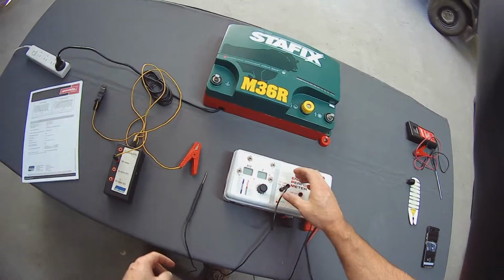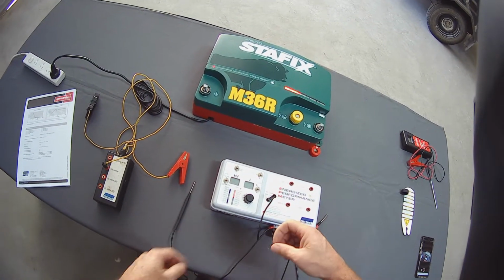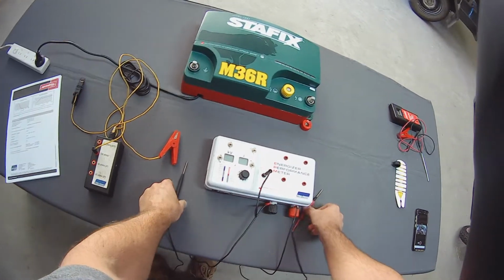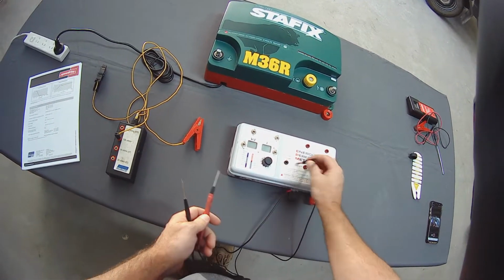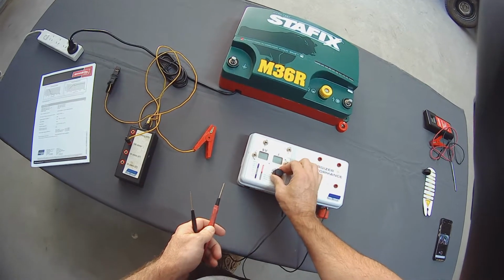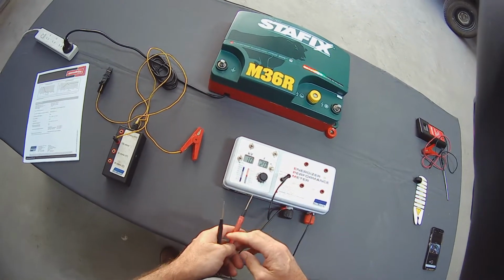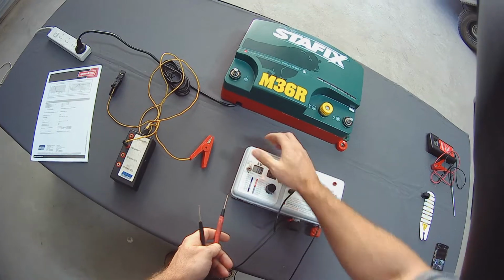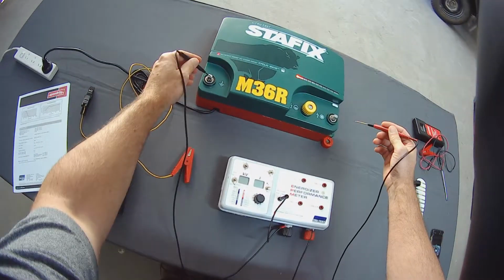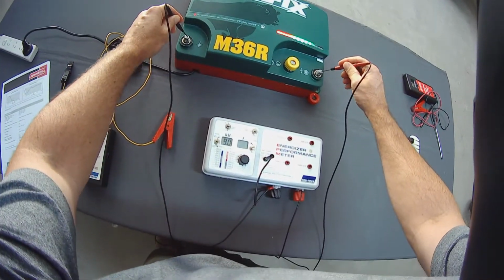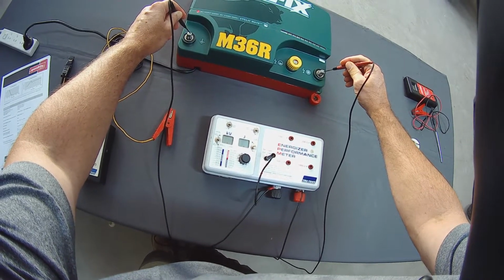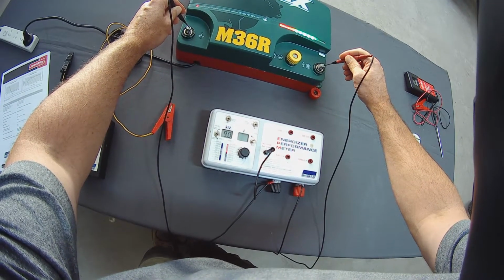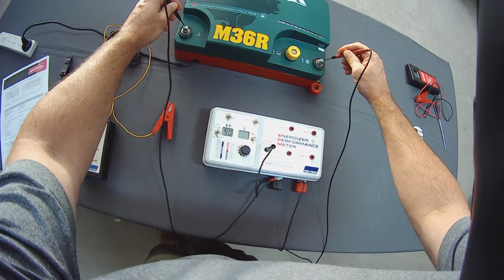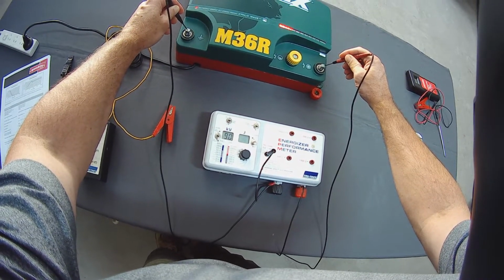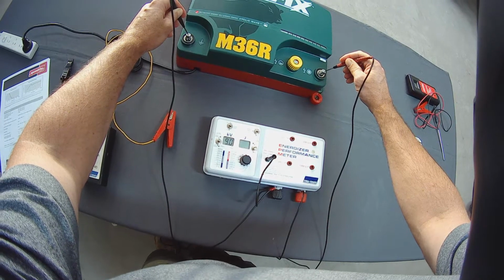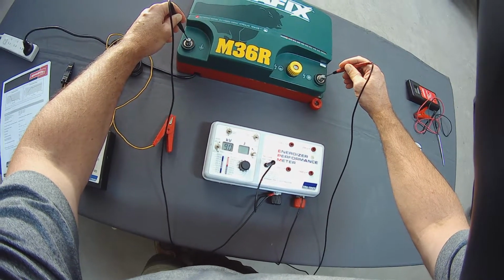So our first reading will be a no load measurement. With our Energiser performance meter, our probe is in the no load port, our dial is set to no load. If we turn that on, all our other switches are up. If we grab the probes, place them on the terminals, you'll see we get a reading there of 9,000 volts. There's no reading in the joules screen because it's an open circuit, so it's not really working very hard at all.